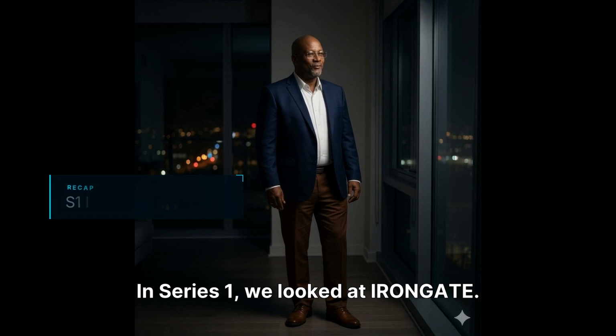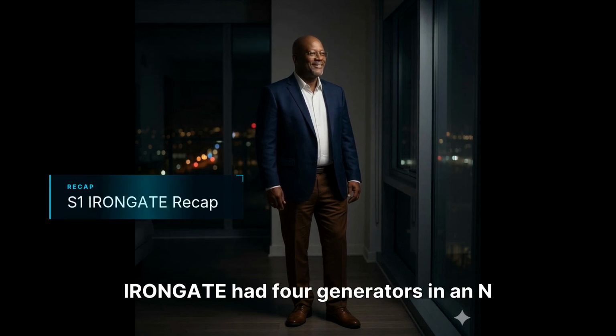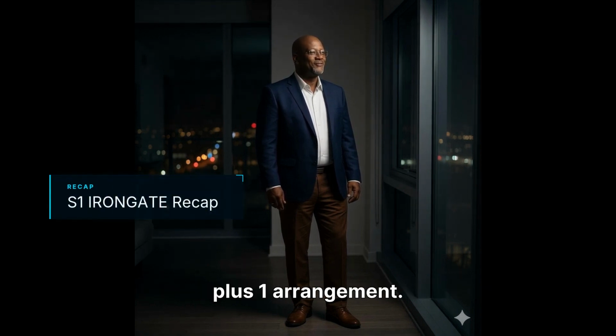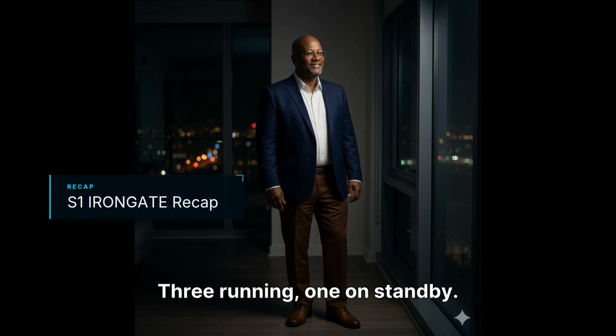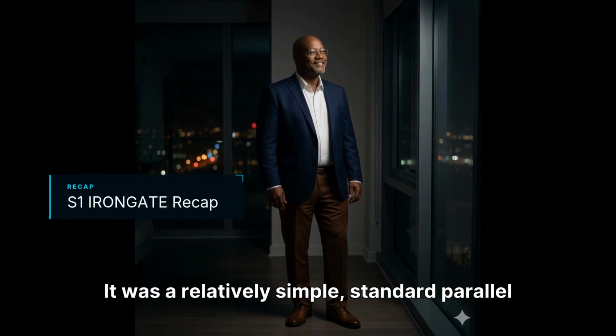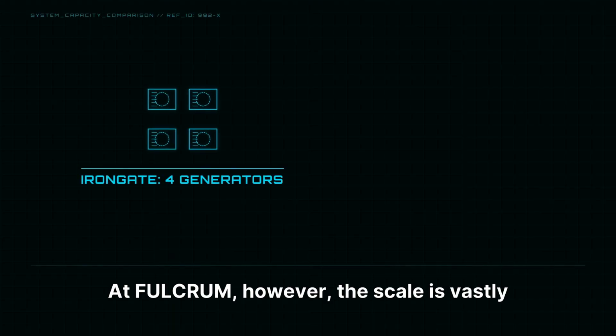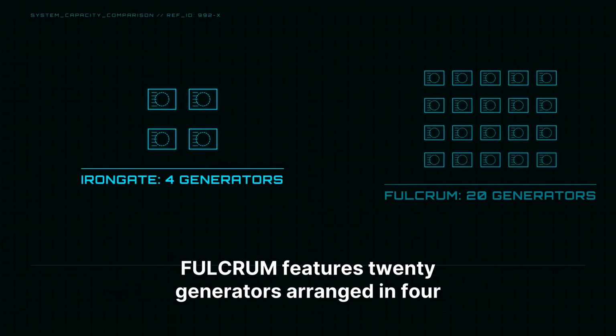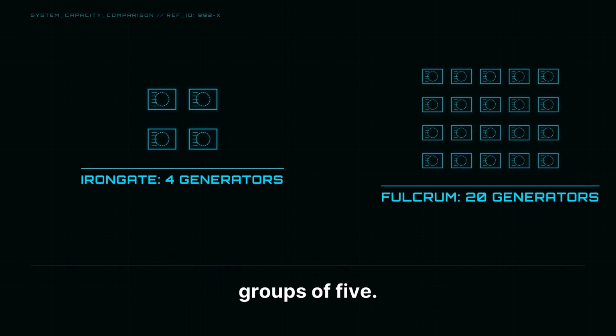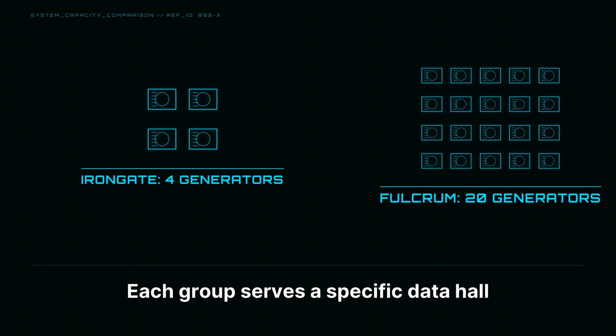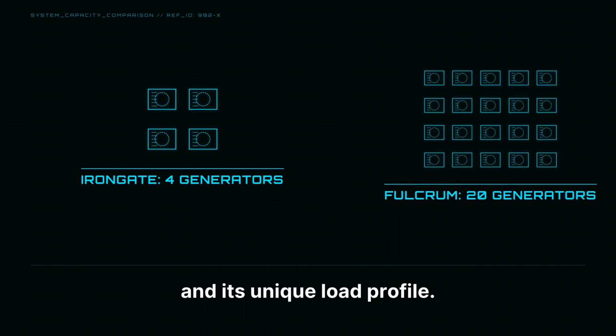In Series 1, we looked at Iron Gate. Iron Gate had 4 generators in an N+1 arrangement, 3 running, 1 on standby. It was a relatively simple, standard parallel operation. At FULCRUM, however, the scale is vastly different. FULCRUM features 20 generators arranged in 4 groups of 5. Each group serves a specific data hall and its unique load profile.